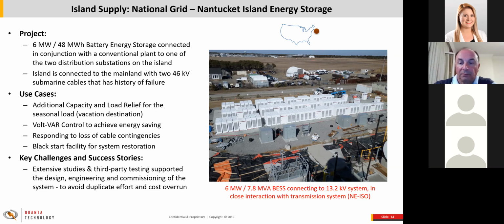In order to address the reliability issue of feeding island customers during a loss of one of the supply cables, and also due to increased demand during vacation season since this is a vacation destination, they installed a 6 megawatt, 48 megawatt hour battery energy storage system connected to their sub-transmission system.